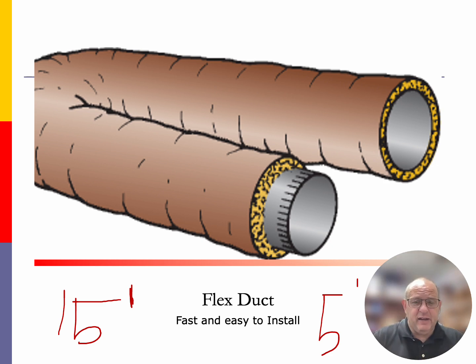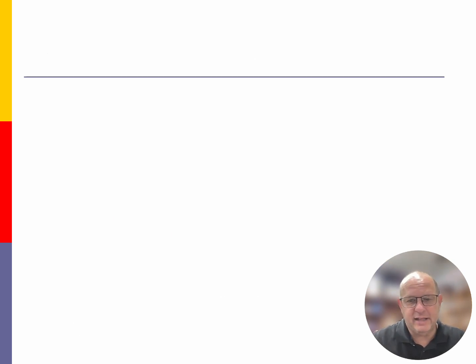Now, the benefit of flex duct is it's fast and it's easy. The second thing is I don't have to insulate it. It's already insulated. So I don't have to run some sock over some metal pipe for my branch runs that are running out there. The insulation is already on there. Easy to hook up, easy to install. Just got to make sure that we're stretched properly so we're getting the proper amount of airflow through that system.